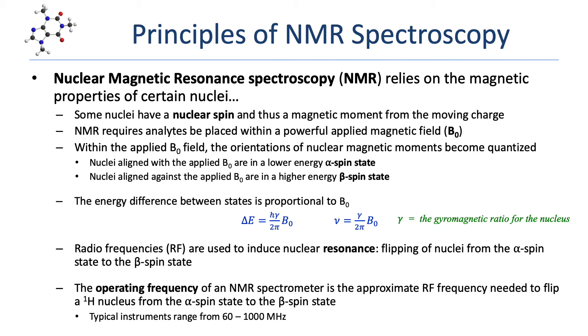An NMR spectrometer measures the frequencies of those resonances. NMR spectrometers are often referred to by their operating frequency, which is the approximate RF frequency needed to flip a hydrogen nucleus from the alpha spin state to the beta spin state. Typical instruments have operating frequencies from 60 to over 1,000 megahertz.